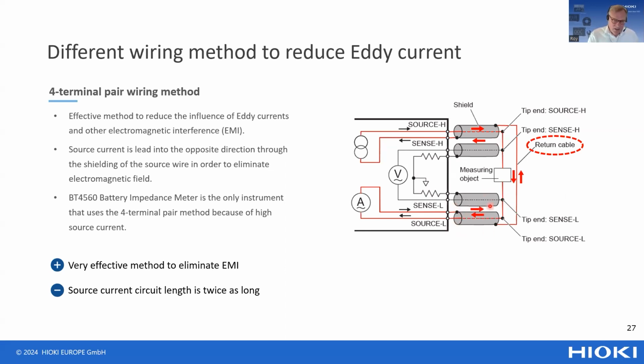And then you can see here, both currents are compensating for the electromagnetic interference. Then we have a connection wire, a return cable, that makes sure that the current is flowing also to the source high shielding of the coaxial cable, and therefore also on the source high side it cancels out electromagnetic interference. Also, we use coaxial cables on the sense side, and that makes it even more robust against external interference from inverters or other equipment in the production line.